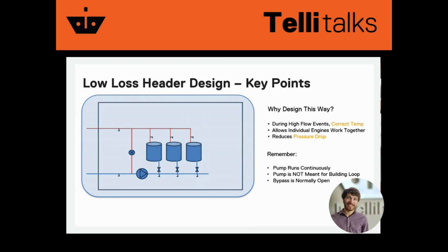Okay, that's important to remember with this design, that the pump is always running. So in the event that there is no external demand through the system, the flow will rotate back through and create a recirculation loop inside of the system. Okay, so flow rate moves this way. The pump is not meant to provide recirculation to the building loop. The pump is a piece of this low loss header design. So it's meant to do those two things. It's meant to force flow rate through my heat exchangers and to recirculate.